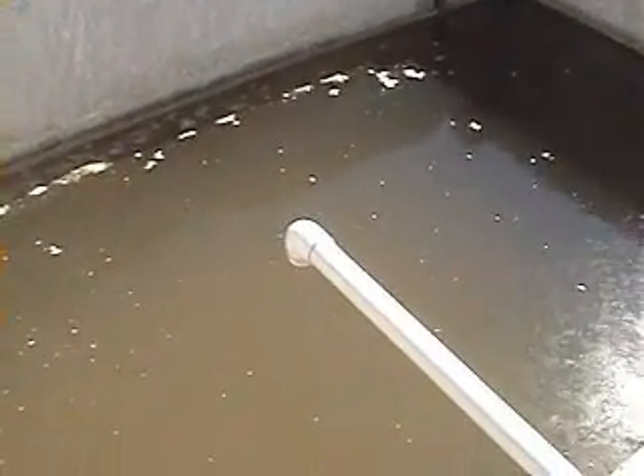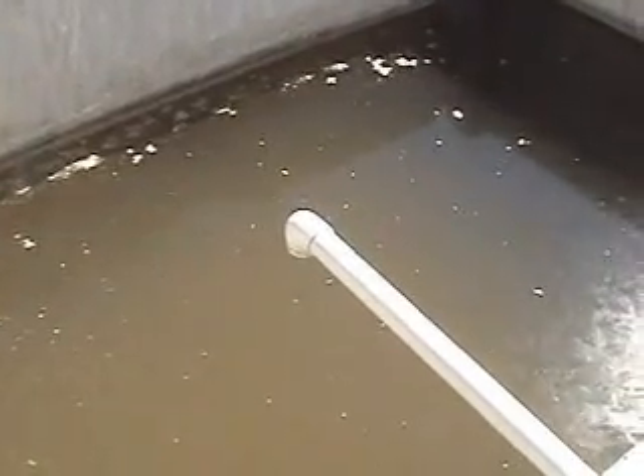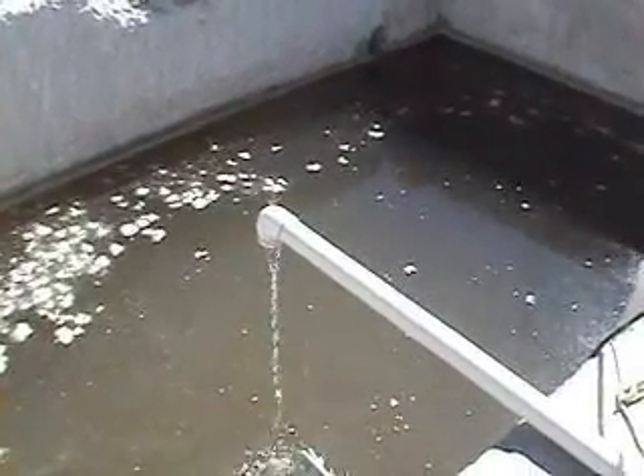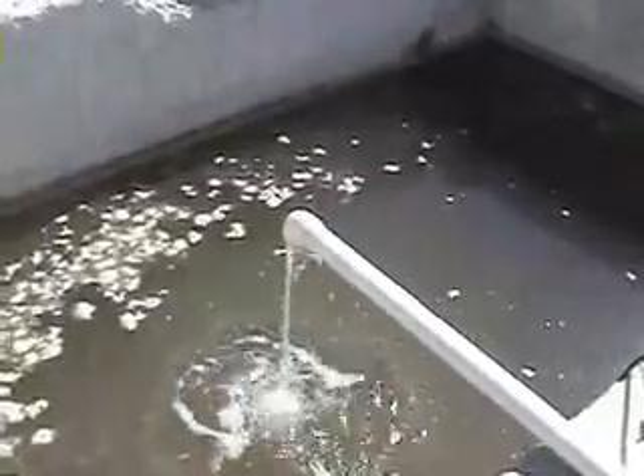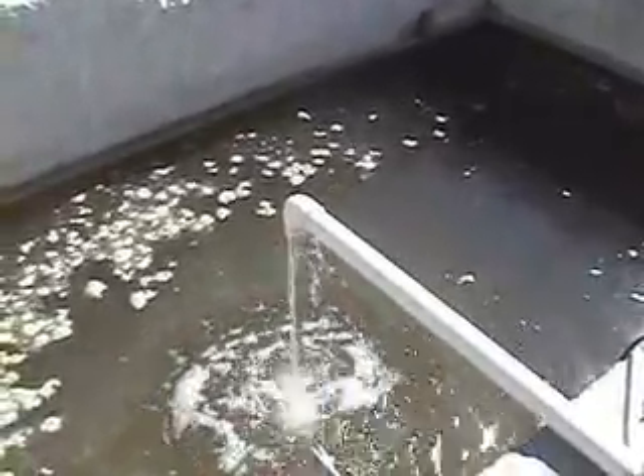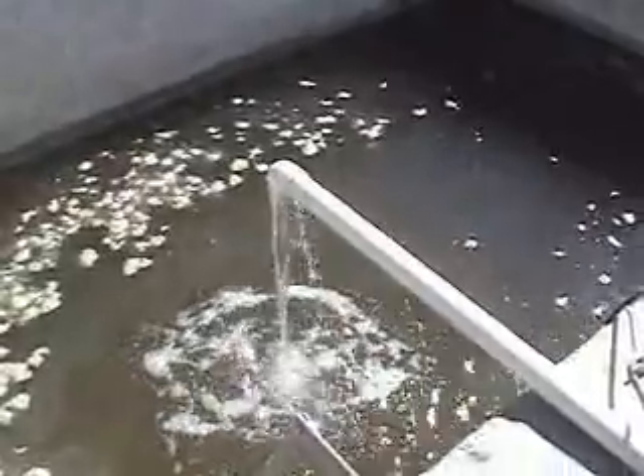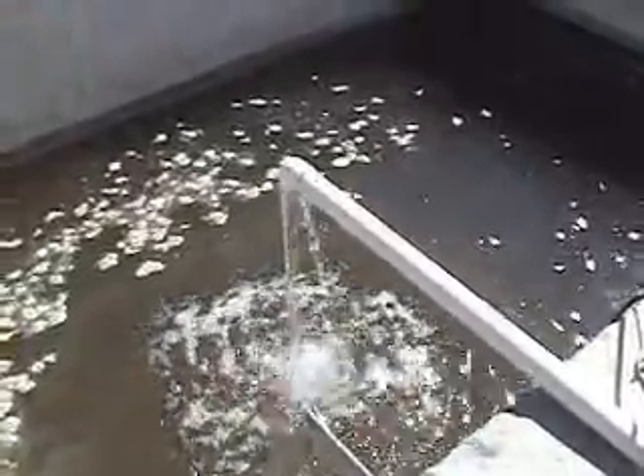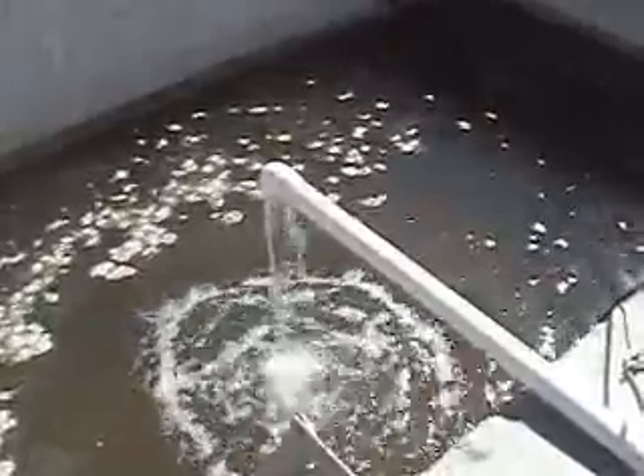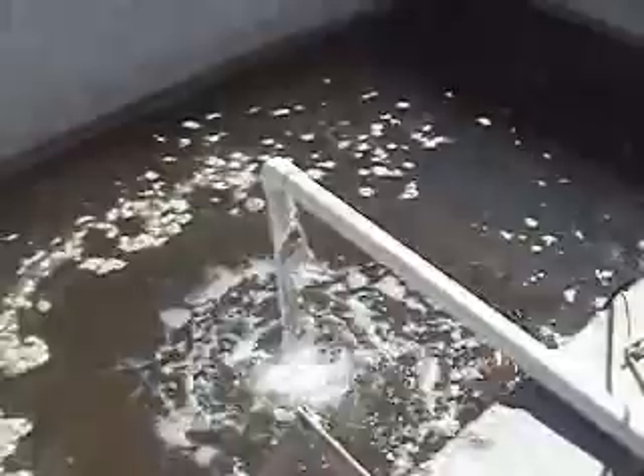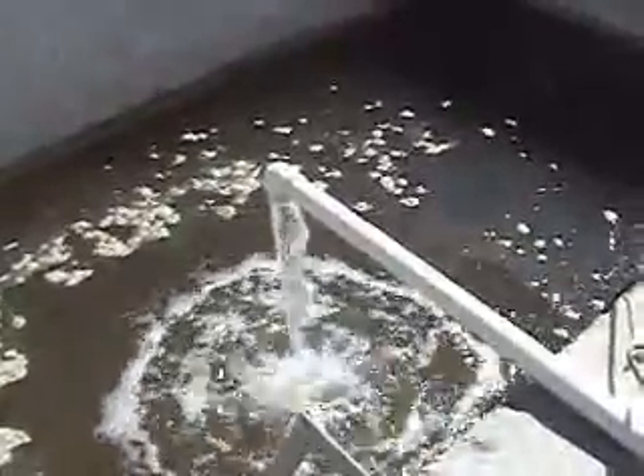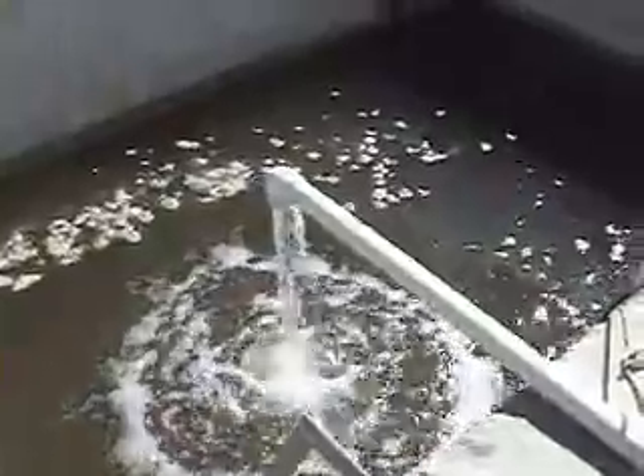Now this is our discharge pipe here. In just a few seconds, the treatment drum here should become full and we should begin to see treatment of the high alkaline sediment water here. Okay, now it looks like the acid storage drum has become full and is now bringing water into our treatment area. Now again, we already have an acceptable pH in this area of 7.5, but if within a couple of days we did not, and we actually had a pH of what the pH controller is reading, which is a pH of 10, it would just take a few minutes for the pH to drop.